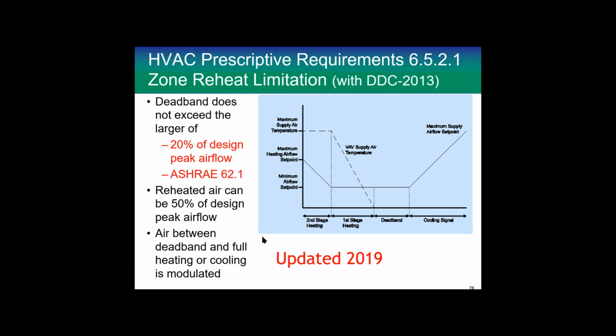Prescriptive requirements for the way we use reheat. It's important. I told you that we do not allow you to heat and cool the same stream, but for VAV boxes we have an exemption. We call this the dual set point, and since 2019, that's the way we require you to do it. So the deadband does not exceed the larger of 20% of design peak airflow, or that required by ASHRAE 62. Now, this gets a little complicated.